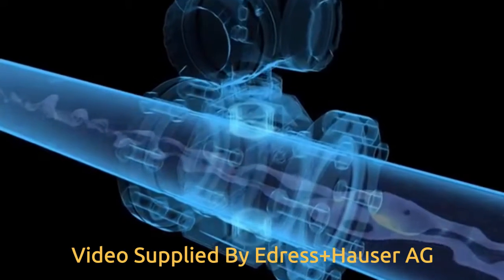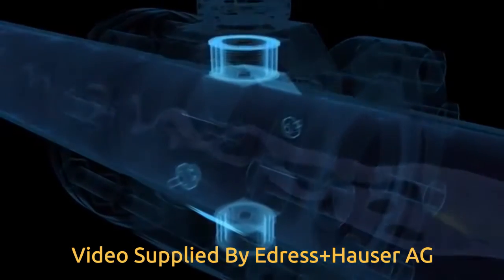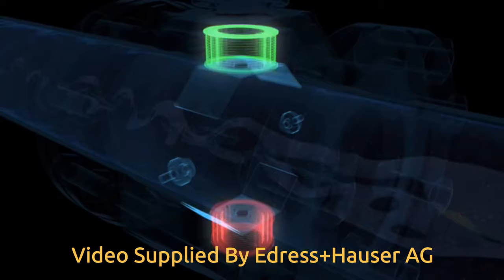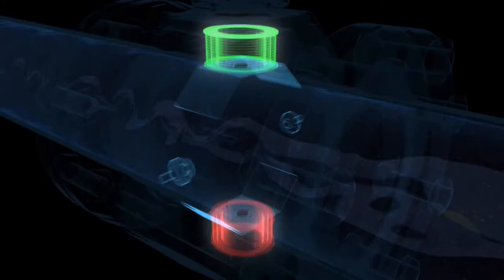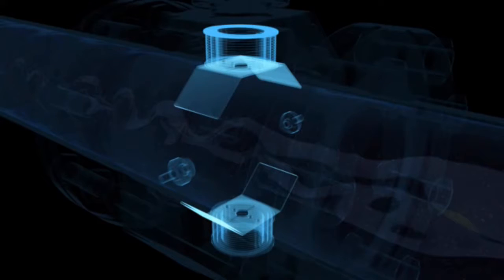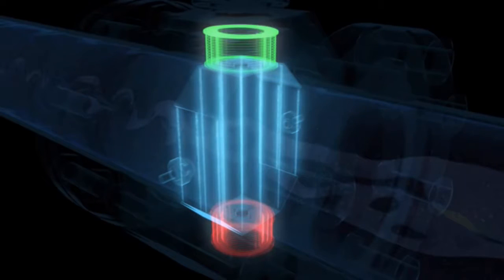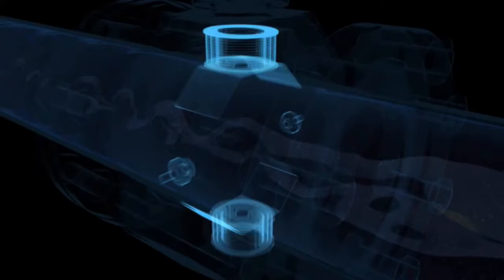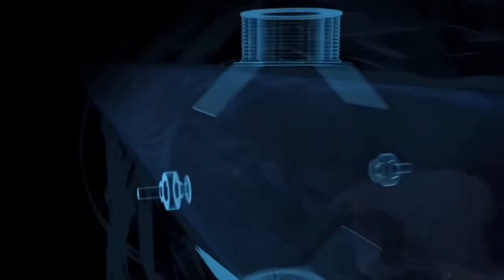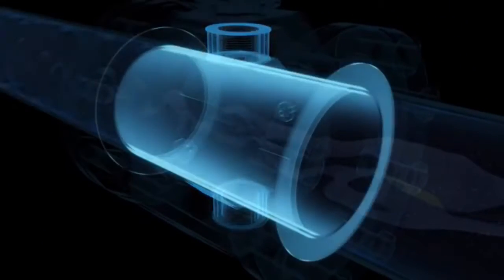Beginning with how electromagnetic flow meters work, two field coils are located inside each flow meter with the help of what are termed pole shoes. These coils generate a constant magnetic field over the entire cross-section of them. Two electrodes which can pick up electrical voltages are installed at right angles of each other in the wall of the tube. There is lining fitted on the inside wall which prevents electrical short circuits in the conductive liquid and the metallic tube.